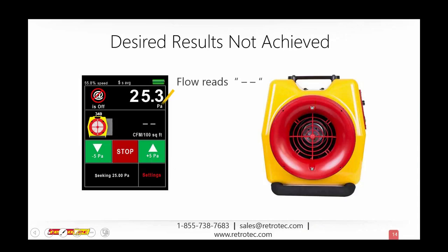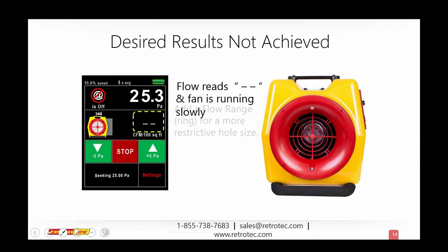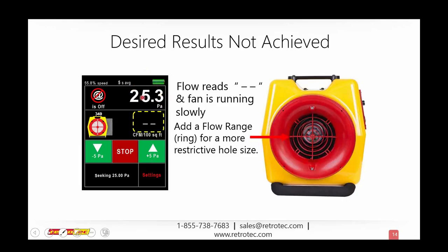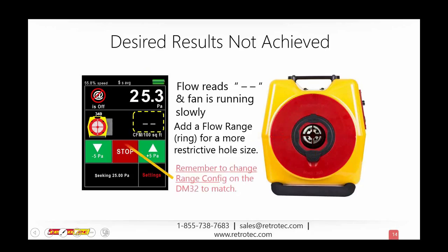So let's talk about some of the desired results. Say your desired results are not achieved. So here what we're talking about is we've actually got to pressure. You can see I'm testing a duct at 25 pascals. So I'm at pressure, no problem. And here in the top left corner you can see that my fan speed's at about 55%, which is perfect. But I'm getting these two little dashes. It's not a zero. It's not like we're just completely lacking. We're actually getting two dash marks. So that must mean that I'm not having any problem getting to pressure in whatever I'm testing here. It's a ductwork, but it could be a house, a shell, a component, a manufacturing piece that you're working on, whatever it is, but I'm not getting any flow through it.